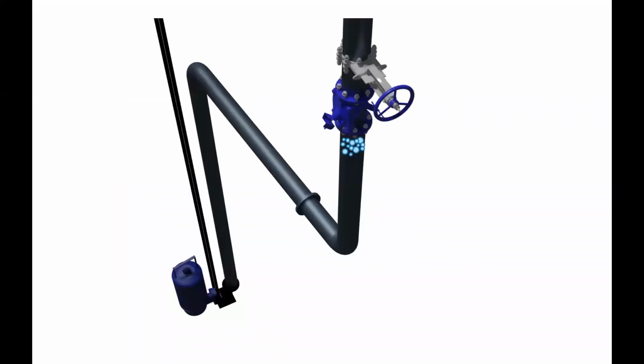It's going to start to hurt because there's a vacuum being drawn. And when I get to that 30 feet or that 9 meters, I'm reaching the vapor point of standard water at standard temperatures, 20 degrees Celsius or whatever. And I'm going to vaporize the fluid underneath that check valve. Now, it's not going to take long. It'll vaporize and it'll balance out.